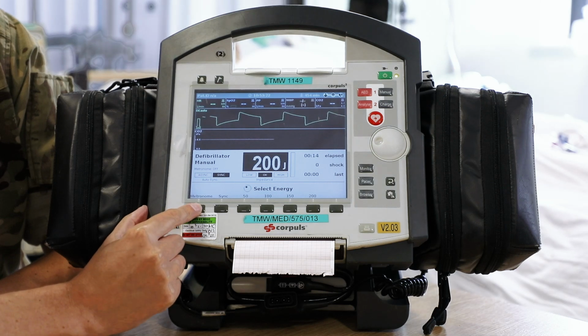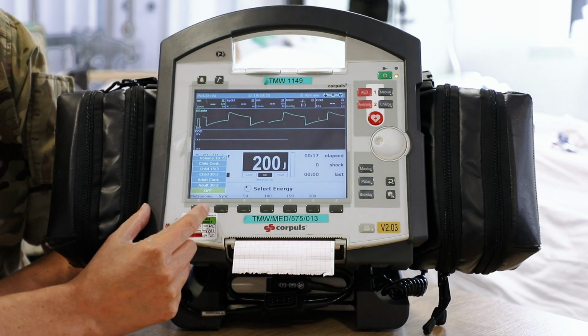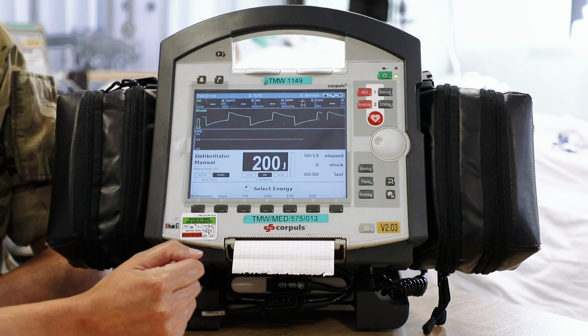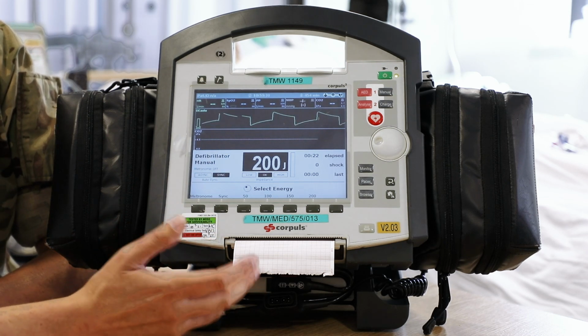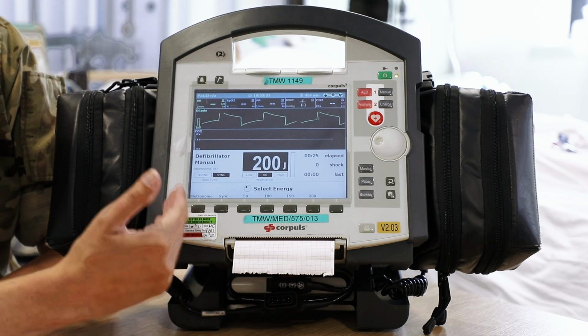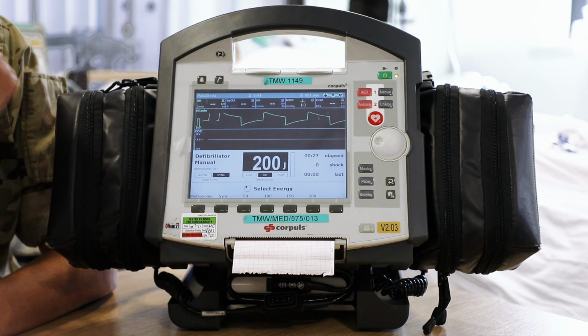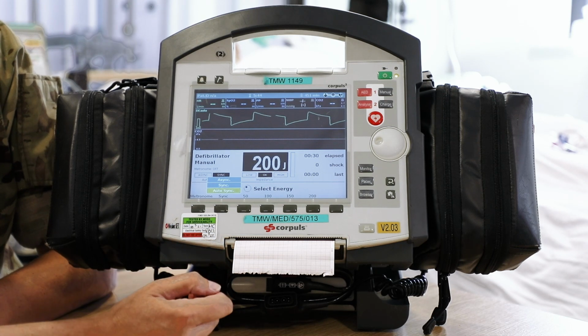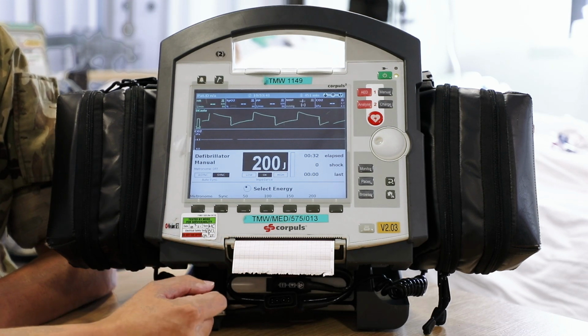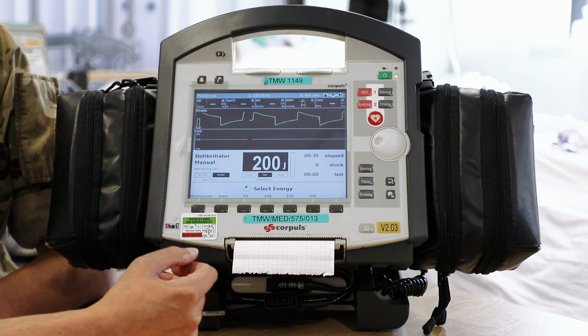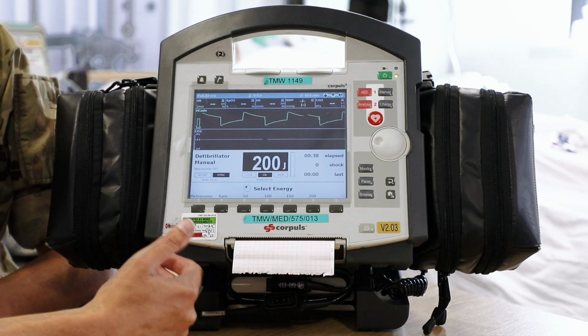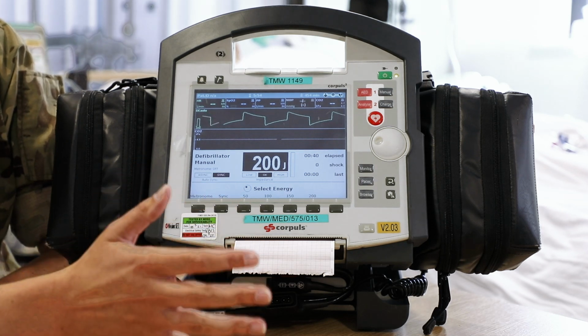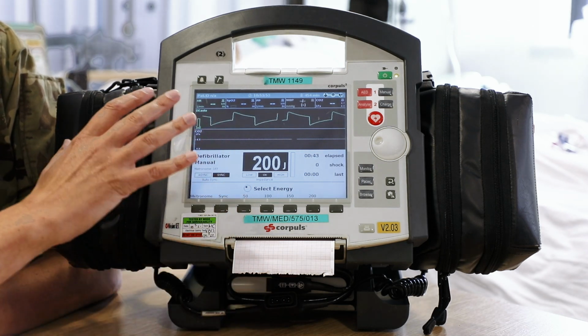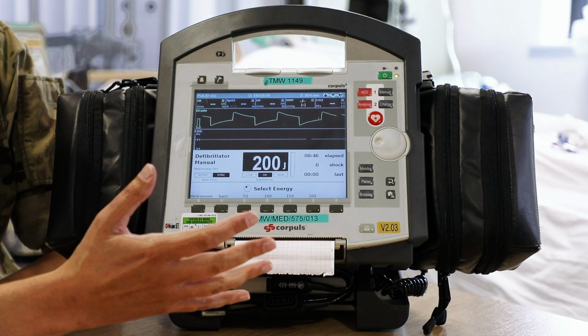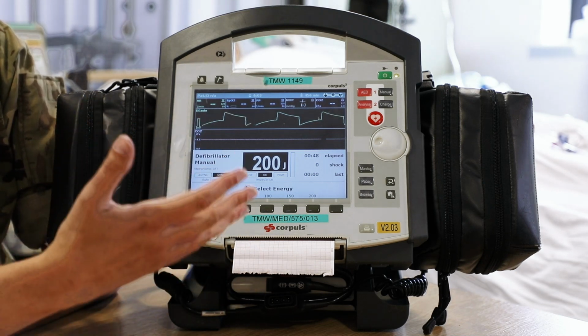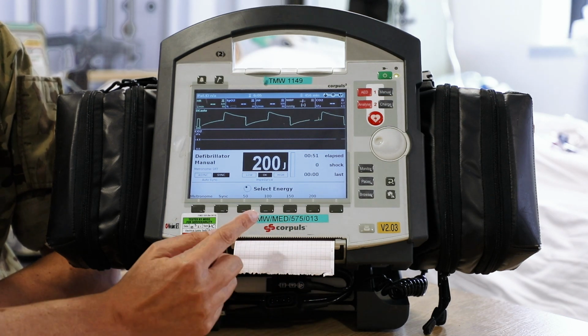So the first option here is a metronome. So you can, if you choose to, listen to the metronome to confirm that it is correct and that what it sounds like is useful to listen to. You should have 2 options in there for adult and child. Our next button is our sync function. So it should be set on auto sync. That just is a nice feature from the Corpuls that means that the defibrillator will always try and automatically sync if you're defibrillating or if you're cardioverting. It's quite clever and will try and do the correct thing for you.